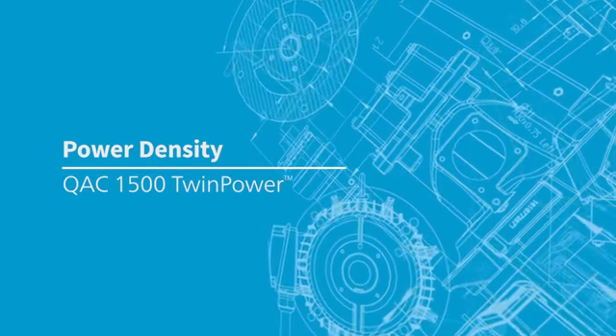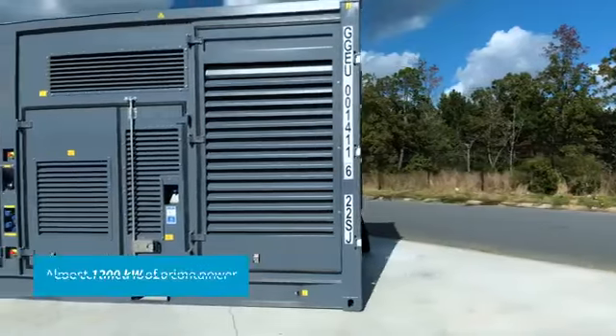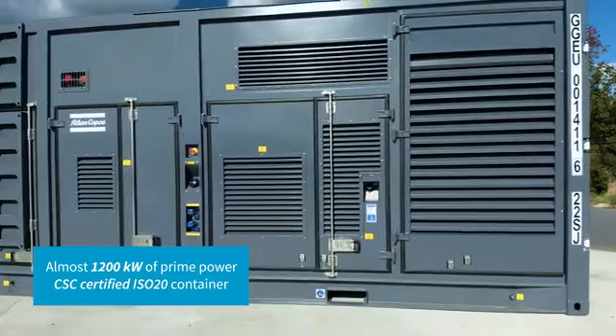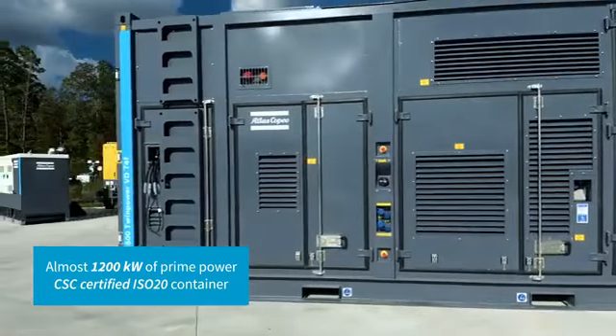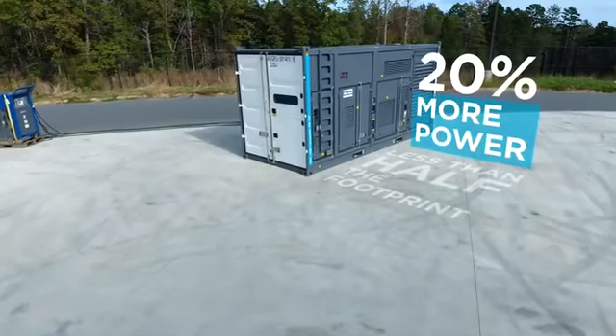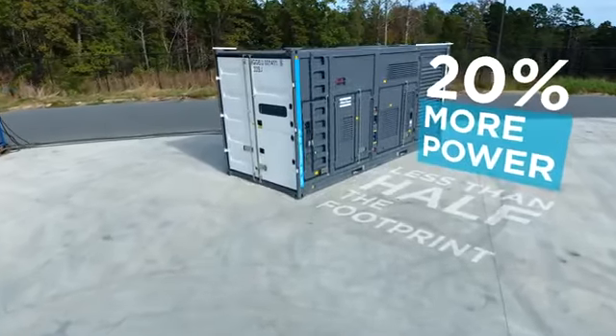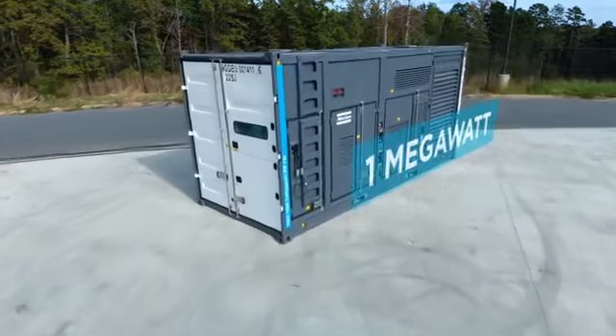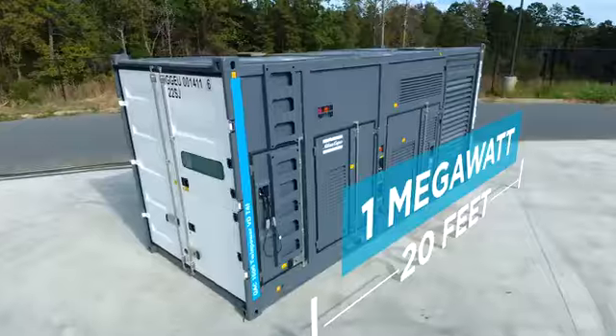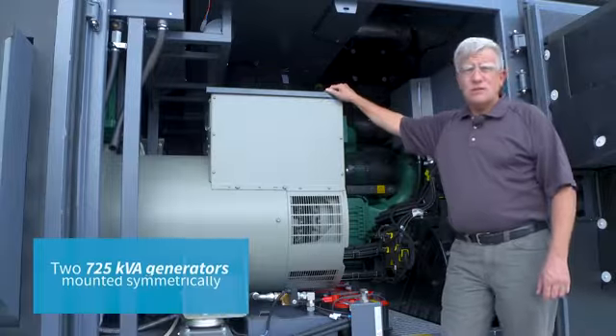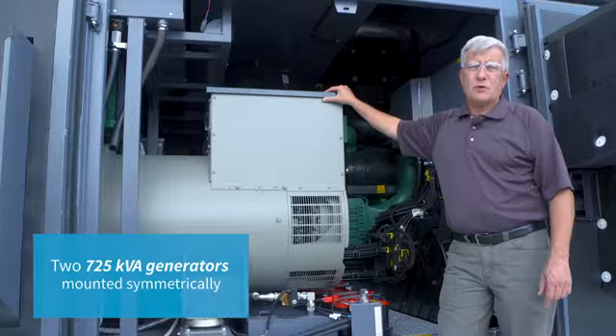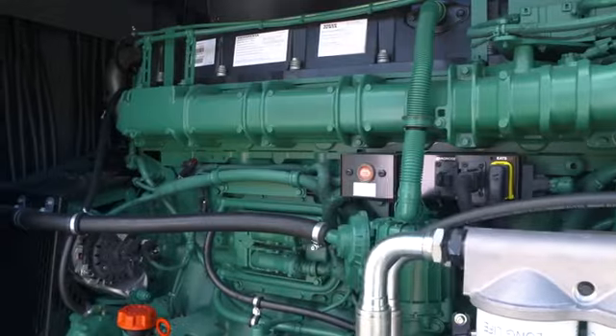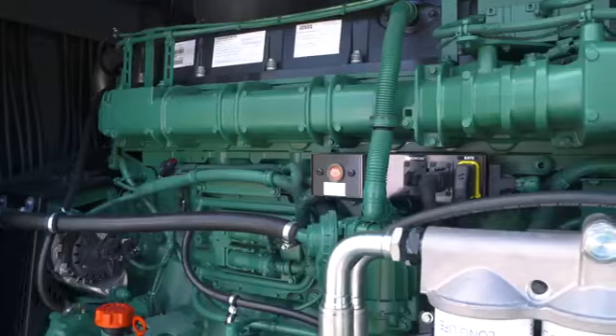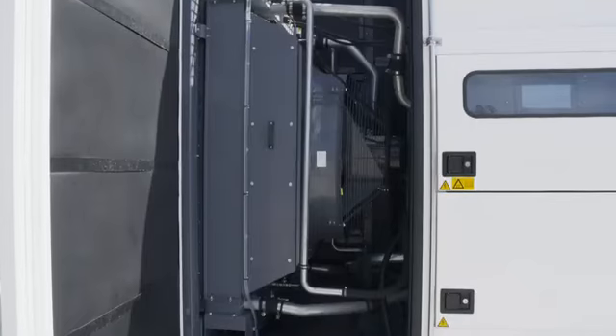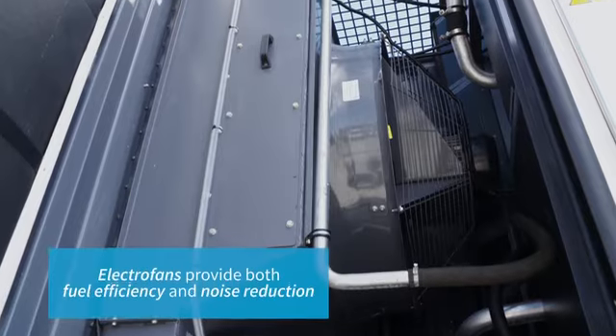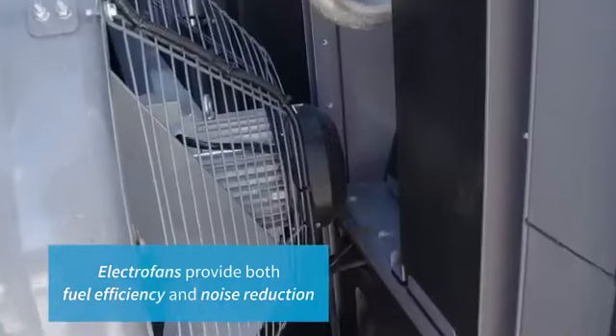Power density. With almost 1,200 kilowatts of prime power within a CSC-certified ISO 20 container, this generator delivers 20% more power in less than half the footprint versus comparable market alternatives. That's more than 1 megawatt in a 20-foot container. Inside, we have two 725 kVA prime power generators mounted in a symmetrical position. Engineered with a 16-liter engine, a more compact exhaust aftertreatment system, and the coolers in a separate room, the addition of electro fans also provides fuel efficiency and noise reduction benefits.